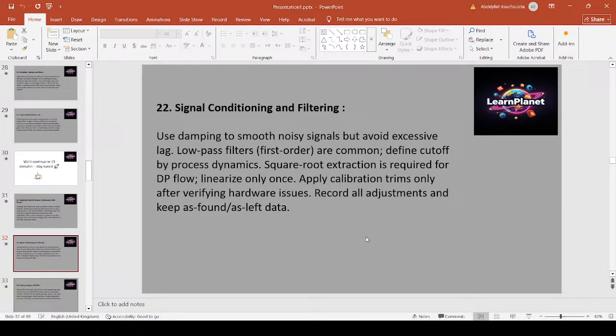Signal conditioning and filtering. Use damping to smooth noisy signals but avoid excessive lag. Low-pass filters are common. Define cutoff by process dynamics. Square root extraction is required for DP flow. Linearize only once. Apply calibration trims only after verifying hardware issues. Record all adjustments and keep as-found and as-left data.